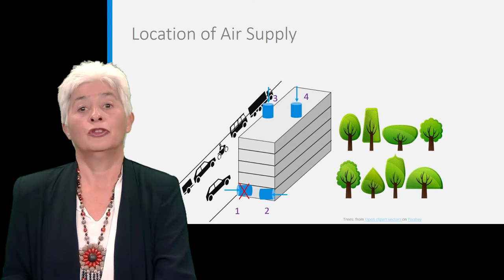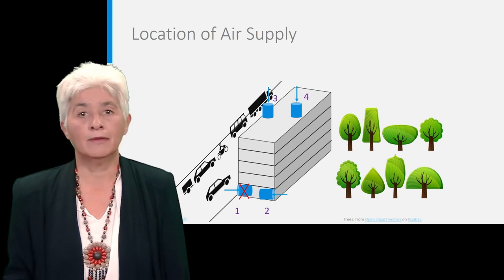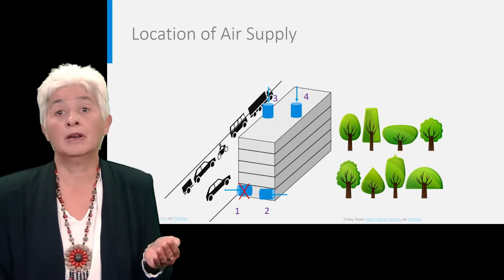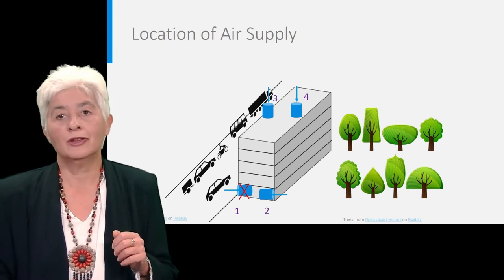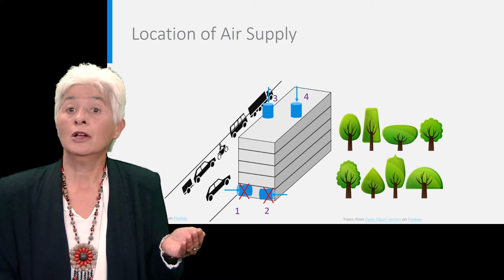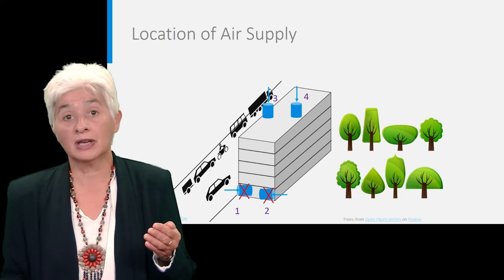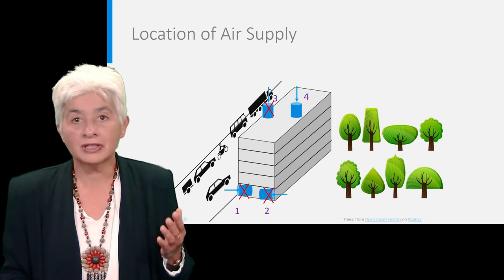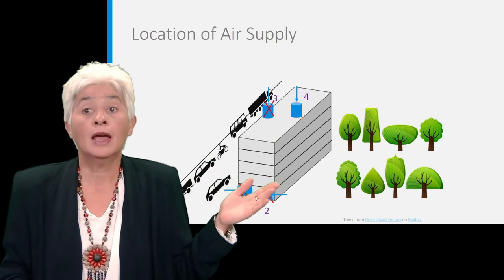Position number two is better. It is at least at the less polluted side of the building. However, an inlet at street level is never recommended as it is more prone to being damaged, clogged, or temporarily polluted, for instance if it is close to a place where people are used to smoke. The higher the air inlet, the less polluted the air will be. So it is always recommended to put it on the roof, preferably at the less polluted side. So better at place four than at place three. And of course you also need to consider the environment and account for pollution sources from other buildings, industrial sites, and the wind direction.